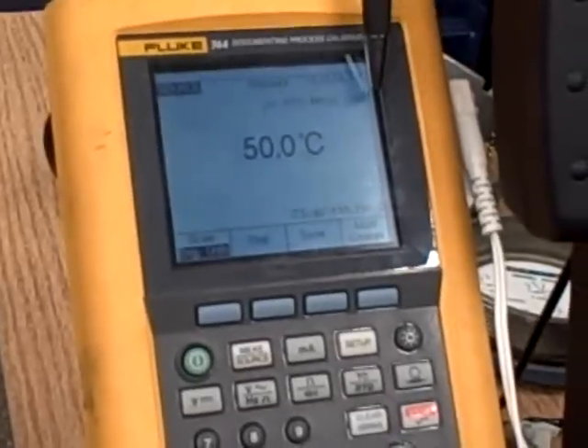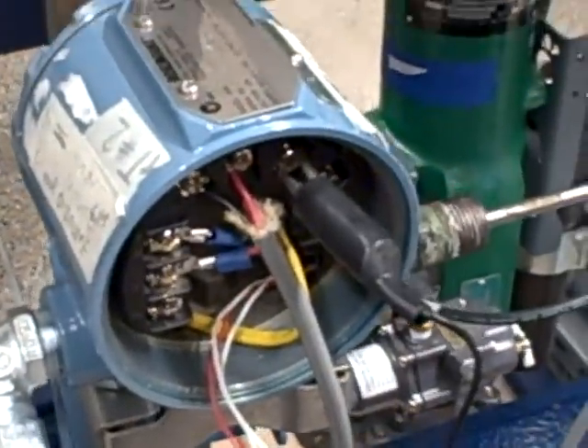Notice it says here, two-wire RTD Platinum 385. We can disregard the two-wire part.